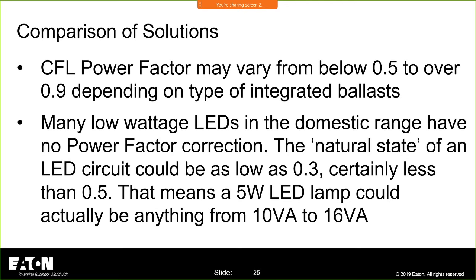Somehow that was missed. And in 220.12, the informational note says the unit values of Table 220.12 are based on minimum load conditions and 100% power factor. That was supposed to be a 0.8 power factor, 80%. The reason I say that is because we did an investigation. Remember, I got the nickname Mr. VA out of this task group work. My point was that these compact fluorescents were not at unity power factor. LED lighting is not at unity power factor. In fact, compact fluorescents and fluorescent lighting in general can be as low as 0.5. If I'm showing you 100 watts with a power factor of 0.5, my VA is actually twice that, because I have to take 1 over the power factor and multiply, and 1 over 0.5 is 2 times. So it's really 200 VA. And that's how we would size our equipment.